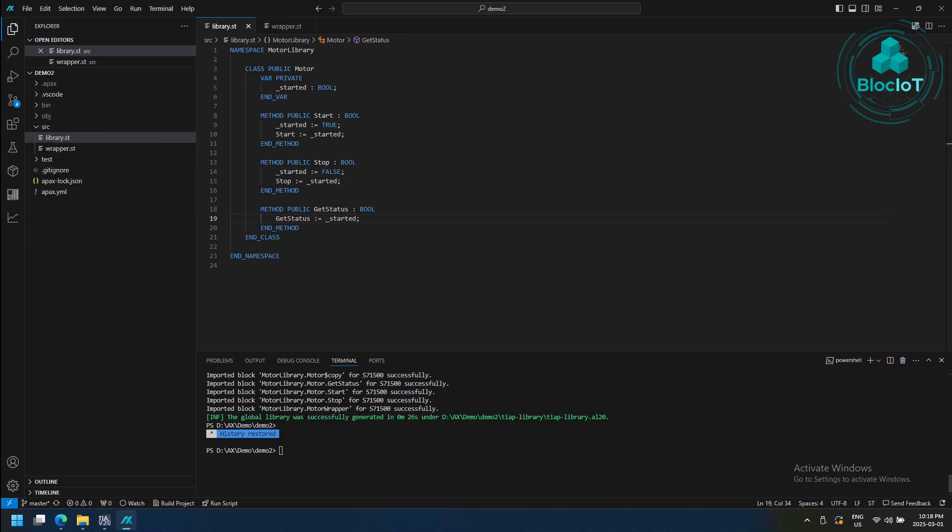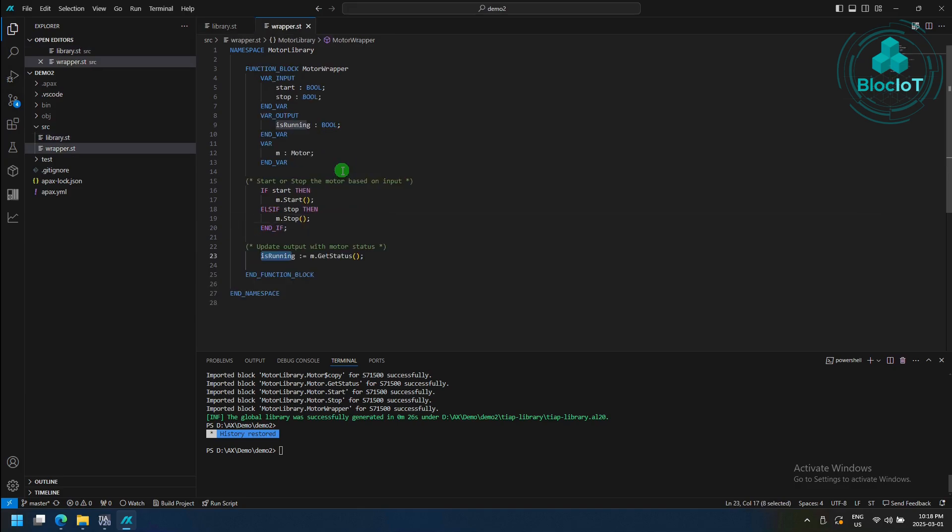The first file, which is the library.st, is a code that can be programmed in object-oriented way with classes, methods, and so on. But because TIA portal doesn't natively support object-oriented programming, we need to create a procedural function block, also called as a wrapper function block.